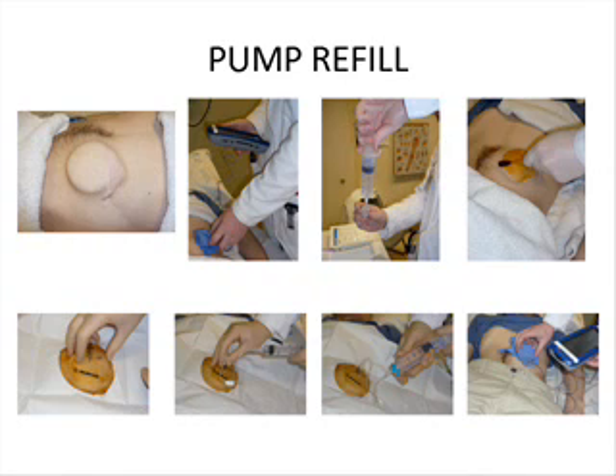So this is actually a set of pictures that I took just last week with an individual who has a very visible pump. Most pumps are not usually this visible. So this is a good example of a pump refill because it's photos, and it's very obvious what we're doing here. So the pump looks like that in the system, and you'll see other people have it a little bit less evident. And there are other techniques to try and bury that a little bit deeper or at least have less potential for skin breakdown over the pump if necessary.